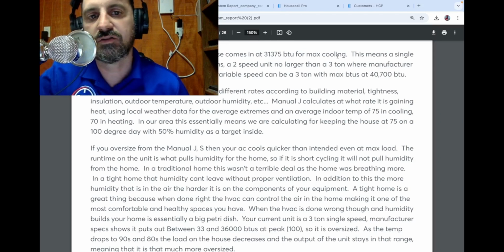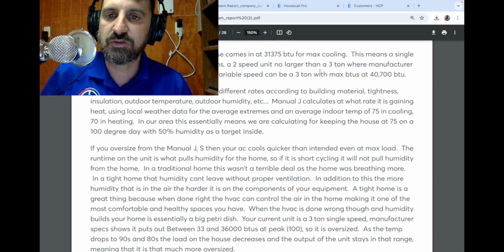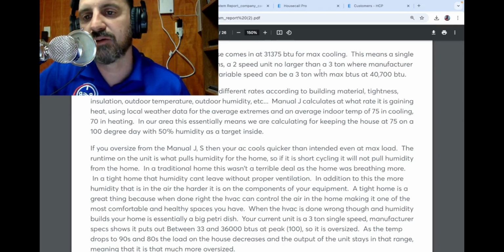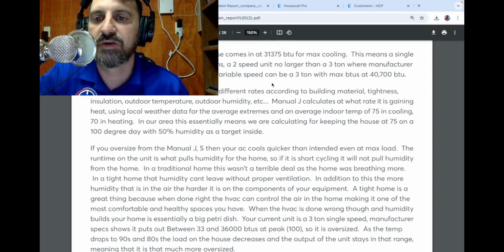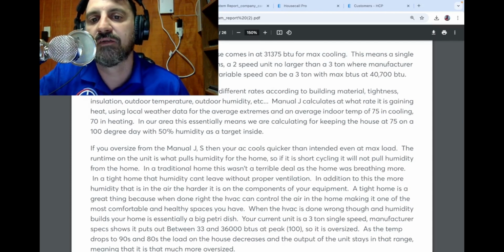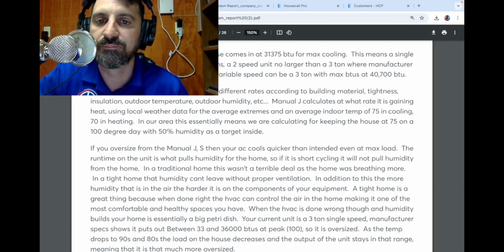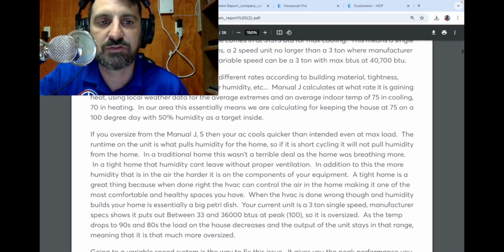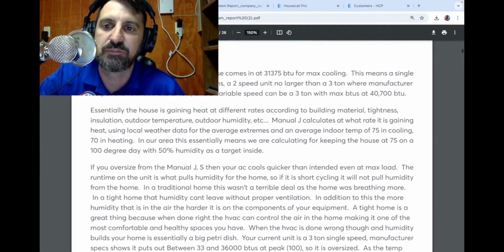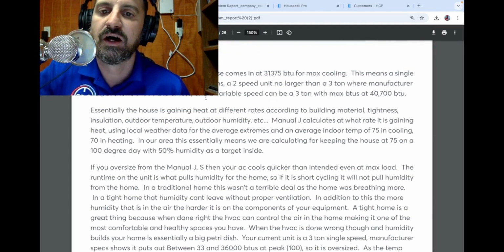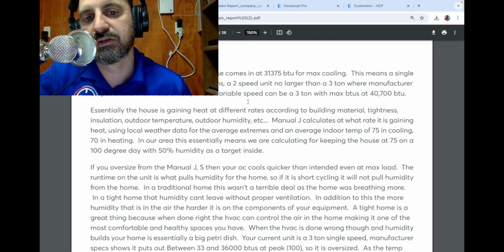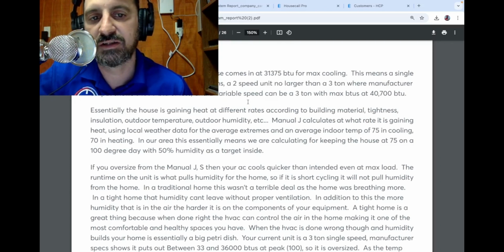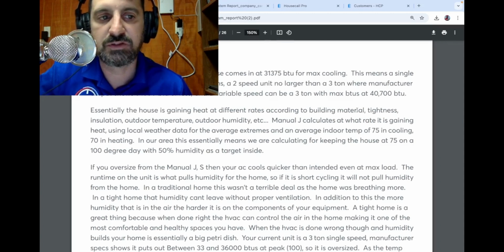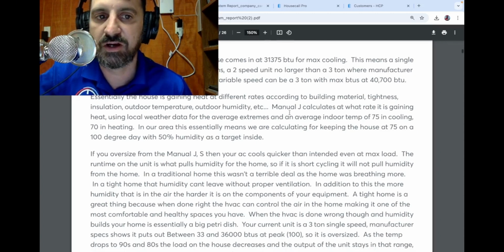If you're using a 2-speed unit, there are some 3 tons where the manufacturer output shows 34,500 BTU or less, and those would work. I'm not a fan of 2 speeds, but that would fall into Manual S and be properly sized. And then a variable speed, which is my preference on any tight construction, can be a 3 ton, but the max output of the BTUs is 40,700.